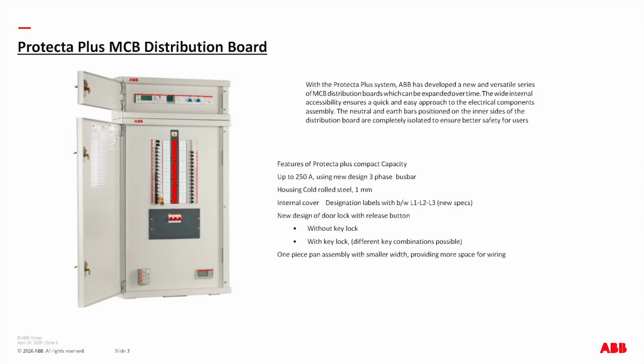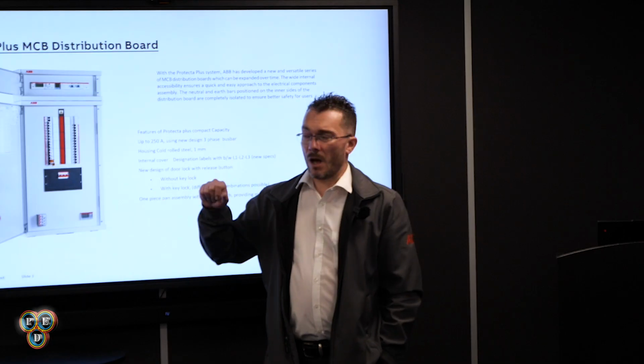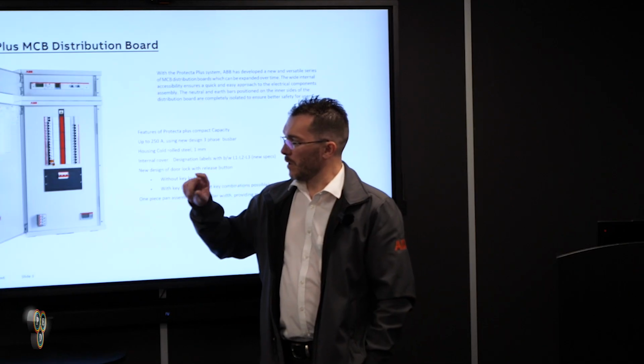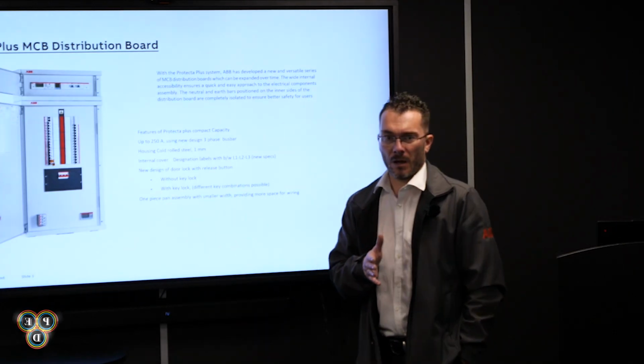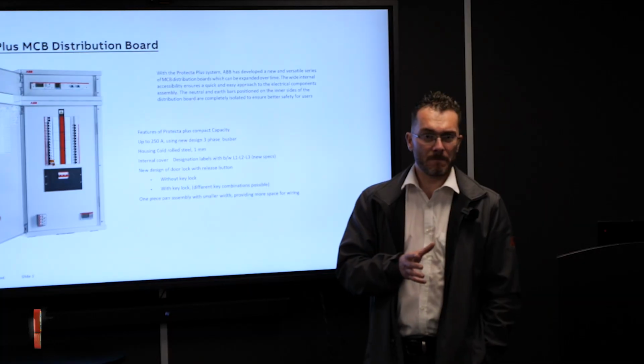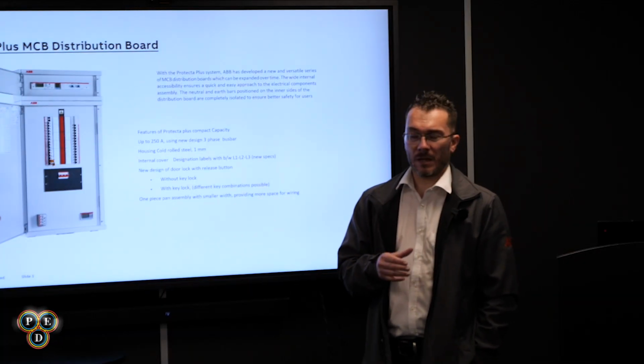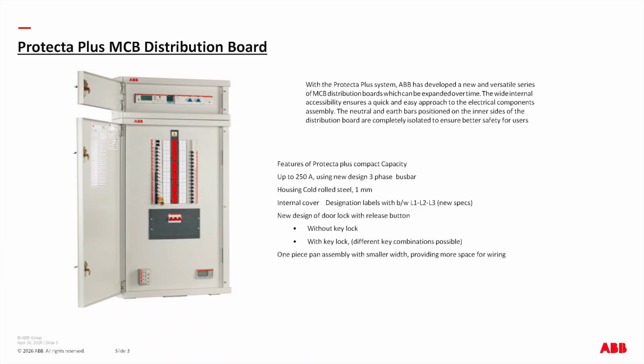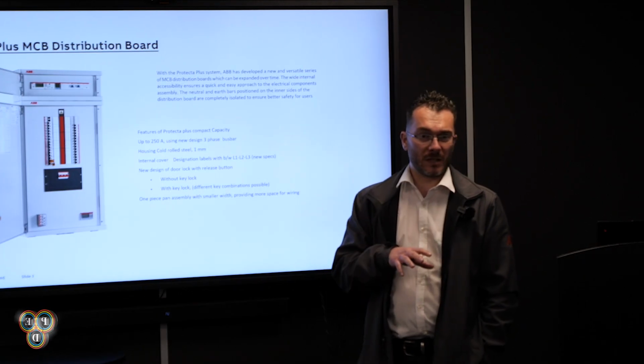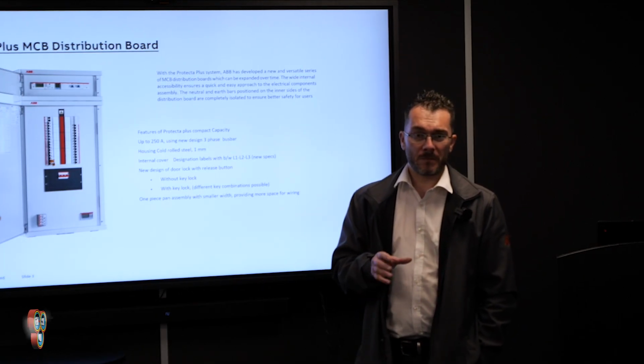Previously we could only do 3-phase incomers, so 3-pole. Now we've got the option of 3-pole and 4-pole incomers, let's say up to 250 amps. So you've got 100 amp, 125 amp switch disconnector, 160 amp MCCB, and 250 amp MCCB in 3 or 4-pole configuration. Any of them will fit directly into the board. There's no need for any extension boxes or anything. In the MCCB incomers, we also offer them as protected devices if needed as well.